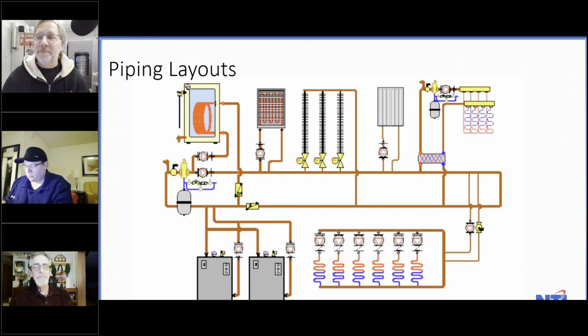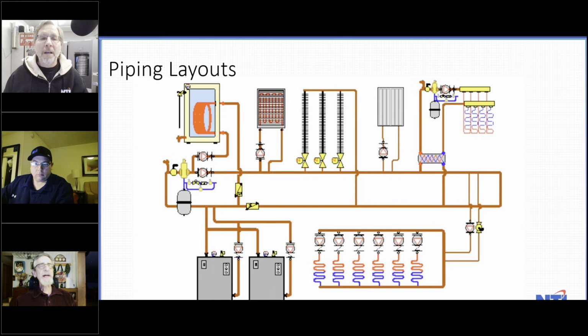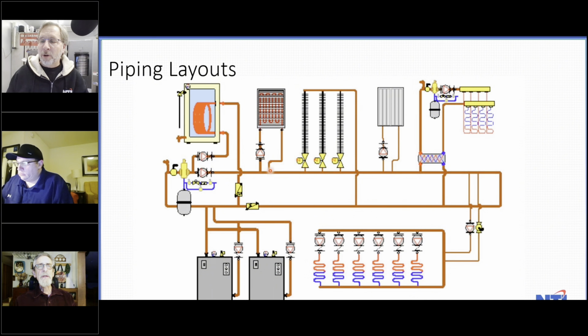So, pretty cool system, Ted. And I forget why this was generated originally. It's an old picture I did a long time ago, but this was somebody's system. I don't remember what it was anymore. But it's a fascinating system to be able to do, to have the boiler pump handling the boilers to 2 closely spaced T's, the pump for the primary loop, which is also handling the plate heat exchanger and the 3 baseboard coils.